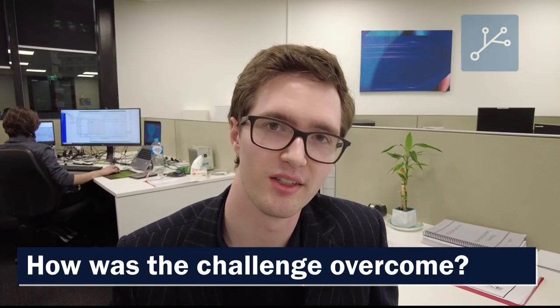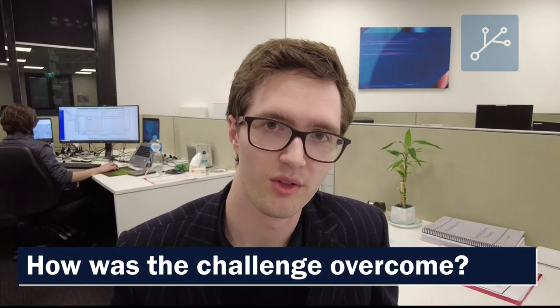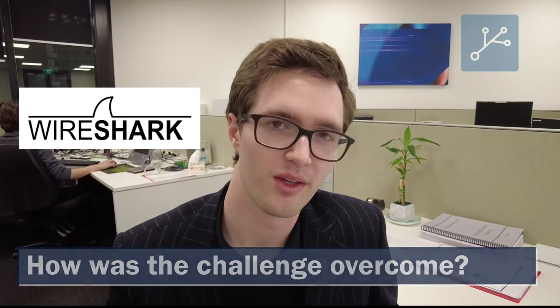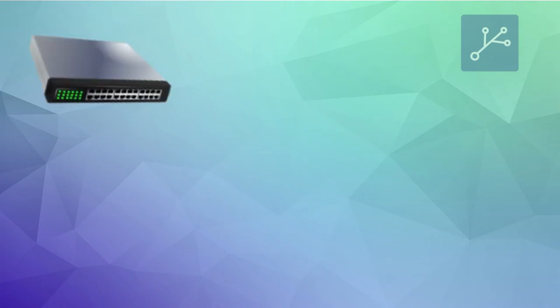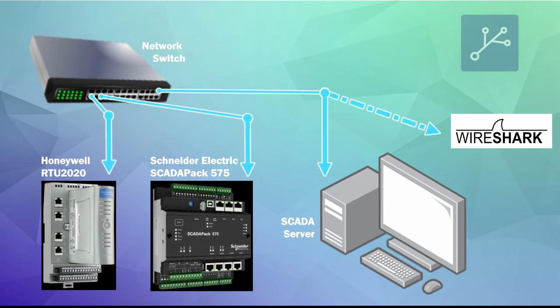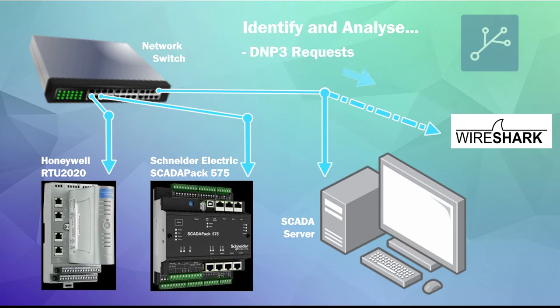Troubleshooting communication was done through Wireshark, where we can see all the different packets sent between the two RTUs. We had a network switch with a mirrored ethernet port, so we can see the outgoing data from the master RTU. For example, we can see DNP3 requests being triggered and verify if the RTU is responding correctly according to our configuration.